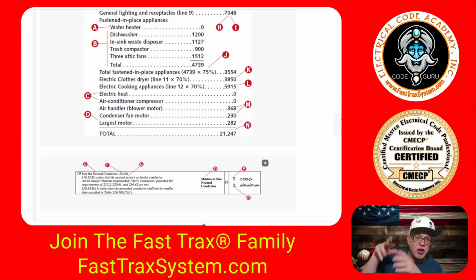Well, since we already took all the motors, we've already taken everything at 100% originally, okay? So I'm just following the rule in 220.50. I'm looking for that additional 25%. That's it. So that's how we get this 282. It is basically 25% of the in-sink waste disposer value.